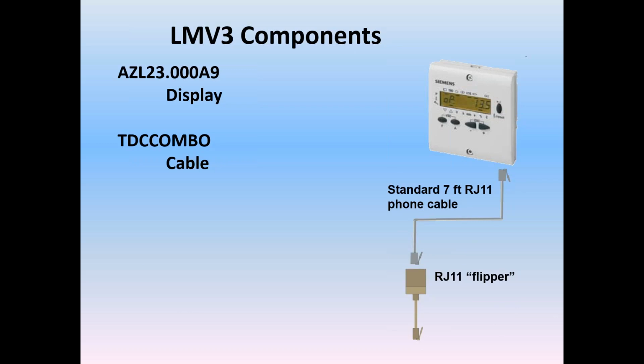What it does is it takes the 4 pins on the cable and turns them over so that 1, 2, 3, 4 becomes 4, 3, 2, 1. So by having a flipper, you can run a 7-foot or a 20-foot or a 3-foot cable as you see fit on the RJ11, and then take whatever cable you get and flip it over so it can be used with the burner controls.